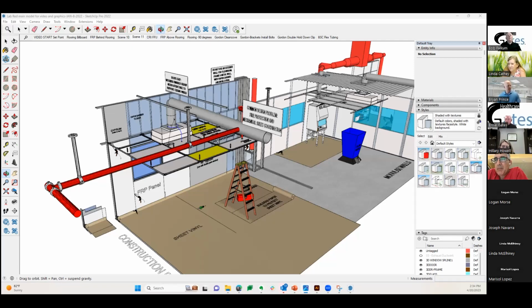When you buy HEPA filters for your rooms, there's a number of choices, but as far as pharmaceutical is concerned, which goes into the pharmacies as well, there's either one which you dispose of in its entirety, which also implies you're taking a 2x4 foot can out of that clean room. I think that's what you're doing. But they do come with room-size replaceable filters where the can stays in place. Not a bad idea to do that.